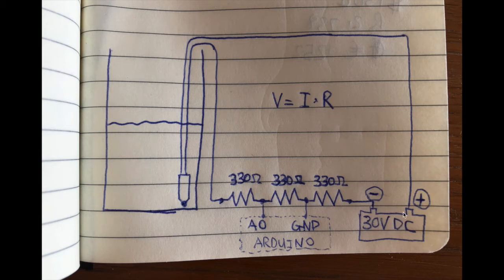This 30 volt DC power supply actually outputs around 34 volts DC. Looking at empty tanks: 3 times 330 ohms times 4 milliamps gives a combined voltage drop of 3.96 volts, so the sensor sees around 30 volts. For full tanks, we get around 14 milliamps, so 3 times 330 ohms times 14 milliamps gives a voltage drop of around 14 volts over the 3 resistors. Taking 34 minus 14, the sensor sees a voltage of around 20 volts.